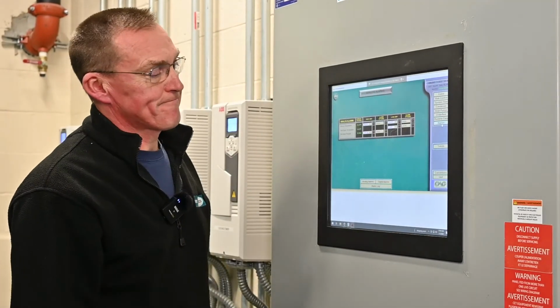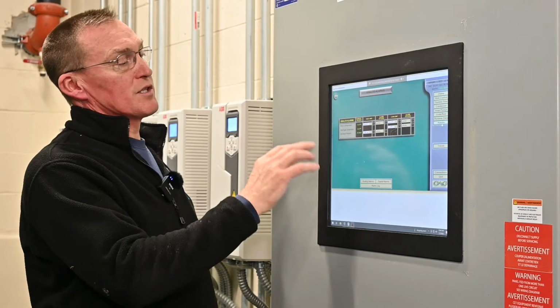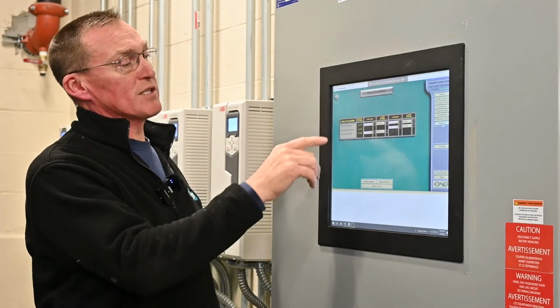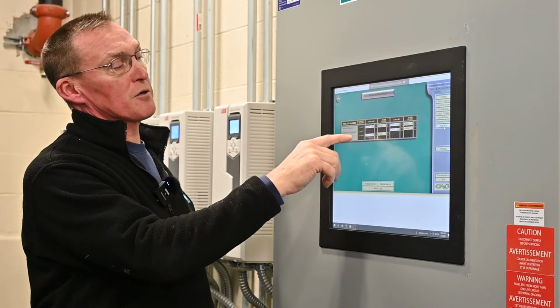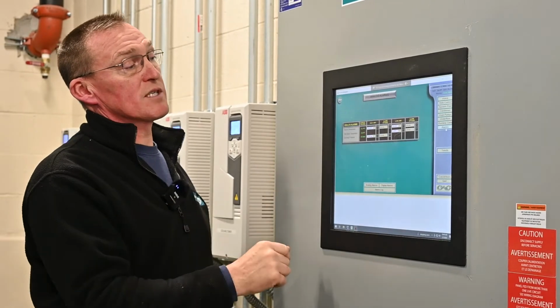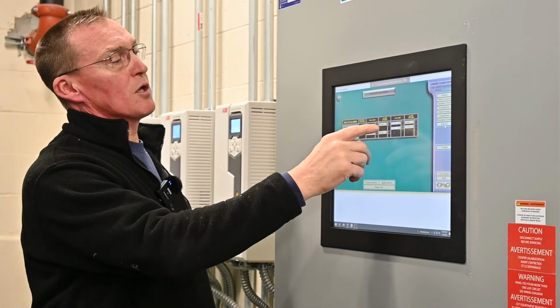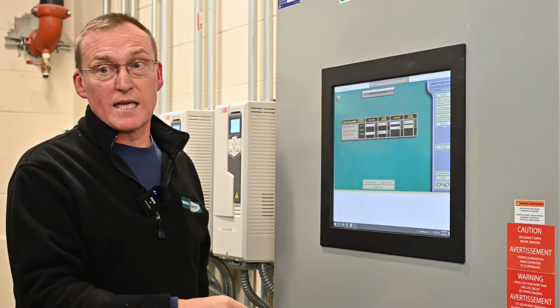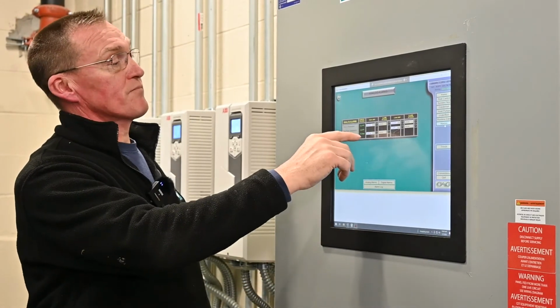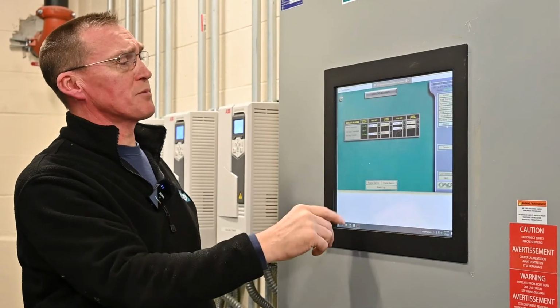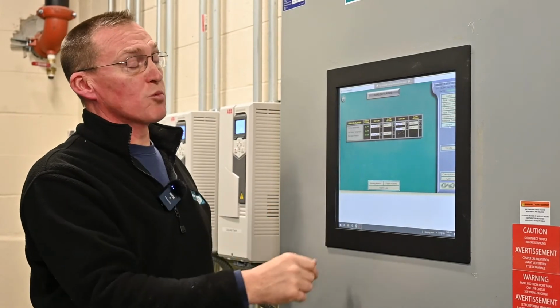Alarms page. This is the analog alarm page. This is basically telling us ice rink temperature, the current reading. What is the high limit? Set for 28. Low limit, 15. That's a cold slab. Rink supply temperature, 14 degrees. The low limit is 1.